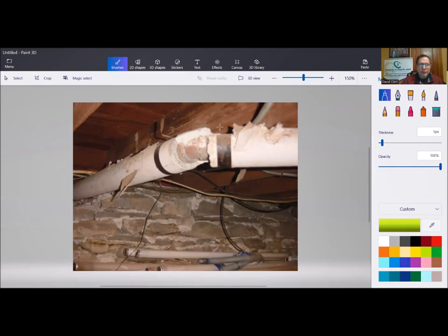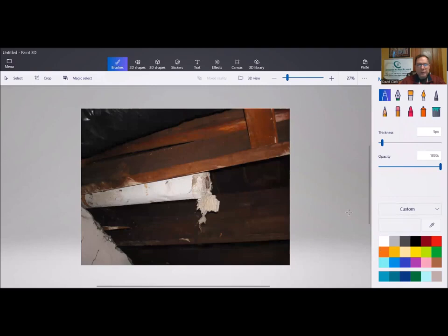But we can see in this case, this would be considered friable, right? Which means it's disintegrating, and probably underneath there it's falling on the ground and airborne. So in that instance, it's going to need to be removed. That whole encapsulation thing has kind of gone out the window, but let me show you some more. And again, same thing. This has been abandoned, which is great. So maybe they ran copper to the boiler or something like that. Still, again, this is all friable stuff, so it's loose, something that we really should probably have removed. Again, we're going to note that it's an unknown material that may contain asbestos, and it should be removed.